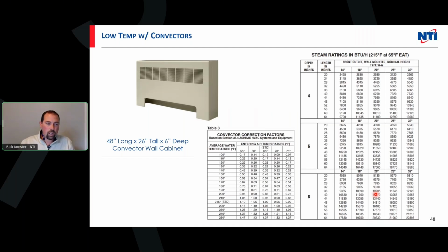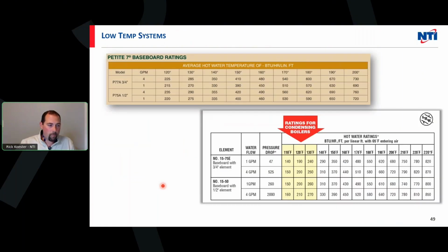Convectors are mostly used for steam, but in the manufacturer's data, they have some correction charts based on water. So that's this chart here, and we can pick various water temps all the way down. You can see what they considered standard was 215 degrees, yet I can do water temps of 100 degrees here. Not that we can't do it, it's just about understanding how many BTUs we're going to get out, and is it going to match what I'm losing. So as long as we're matching it and offsetting those numbers, we can maintain a thermostat setting, right?